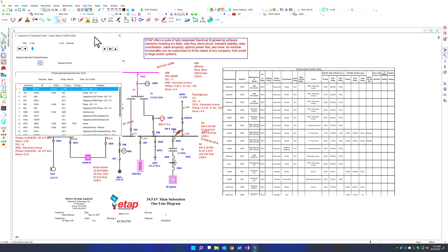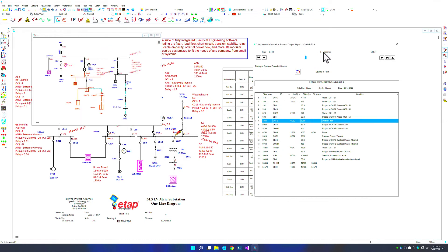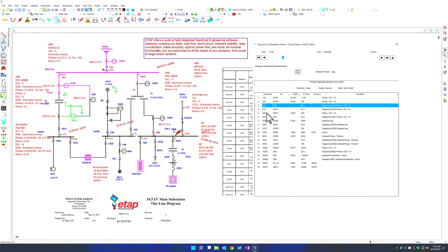Star also includes a brand new sequence of operation slider that allows you to review the sequence of operation for large and complex systems in a very easy and convenient manner. Once you run the Star sequence of operation, you get the sequence of operation event list. From this list, you can pick a particular component and the program will move the slider, showing you at what time that event happened — in this case at 5 seconds — and highlight which device operated. You can pick another device, such as circuit breaker 8, which is tripped by overcurrent relay number 7, and the program will flash and indicate this is the first device that tripped in the network.